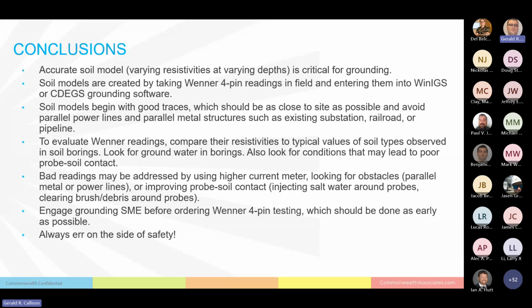To evaluate your Wenner readings, compare the resistivities to typical values of the soil types observed in boring reports. Look for things like groundwater or anything that might affect probe-to-soil contact. If you have bad readings, maybe they can be addressed by using a higher current meter, looking for obstacles like parallel metal or power lines, and improving probe-to-soil contact—you might inject salt water around the probes, or clear brush and debris around them. And engage your grounding SME before ordering the Wenner 4-pin tests, so you can head off issues and learn from the SME's experience.